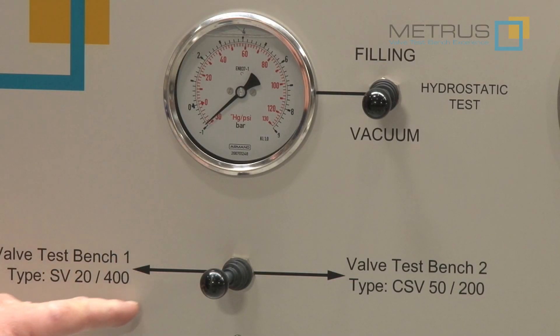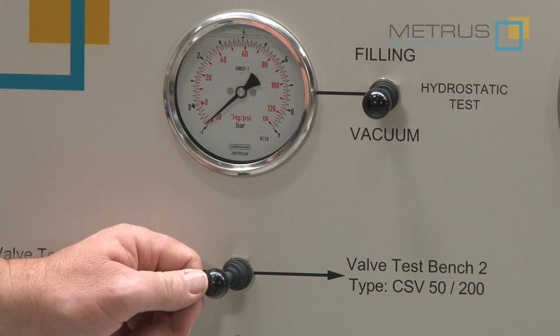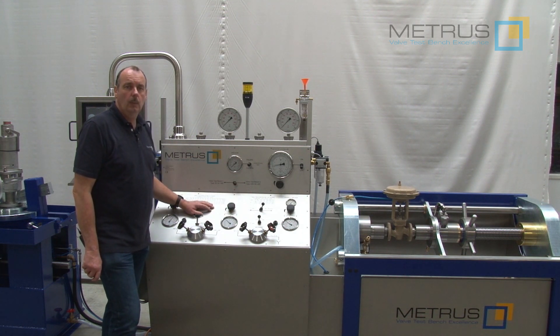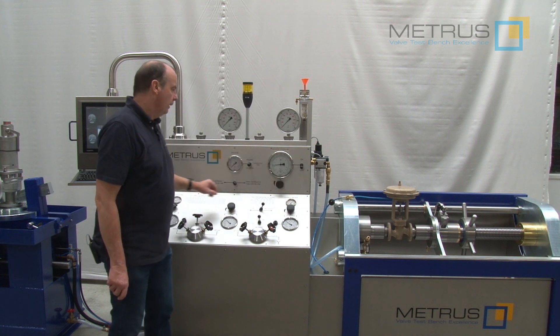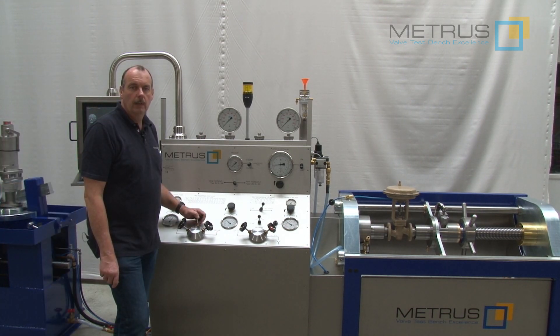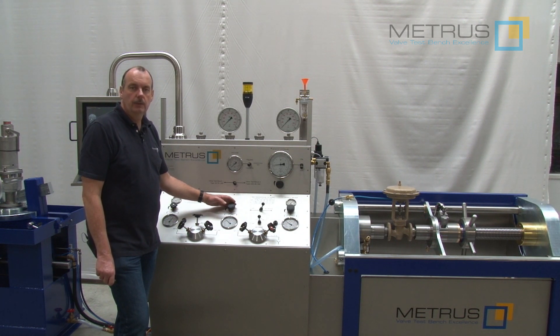If you would like to work now with the control and shutoff valve test bench CSV 50/200 instead of the safety valve test bench SV 20/400, just switch over to the right hand side. Now you can operate the CSV control and shutoff valve test bench via the control panel on the right hand side. Also here we are able to perform high pressure water tests, low pressure air tests for seat leakage, and you can also control the actuator of the valve pneumatically. All test values will be shown and recorded on our computer registration system CRS. If you are interested to learn more about how to operate the control valve test bench CSV 50/200, please visit our website and go to the video section tutorial videos — there you can find a video called how to test the control valve.